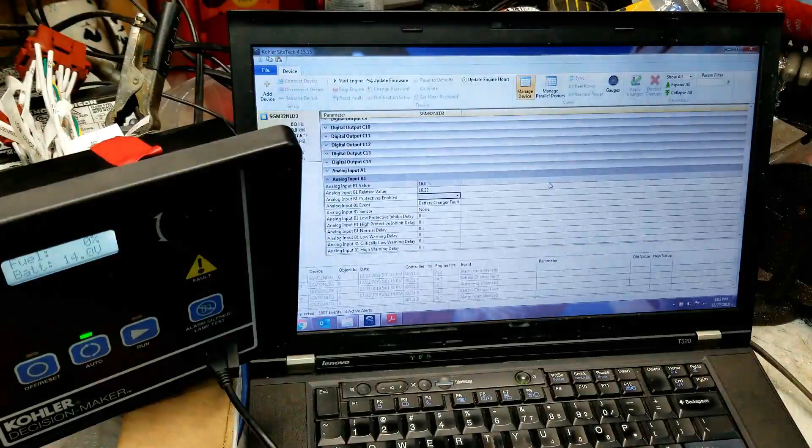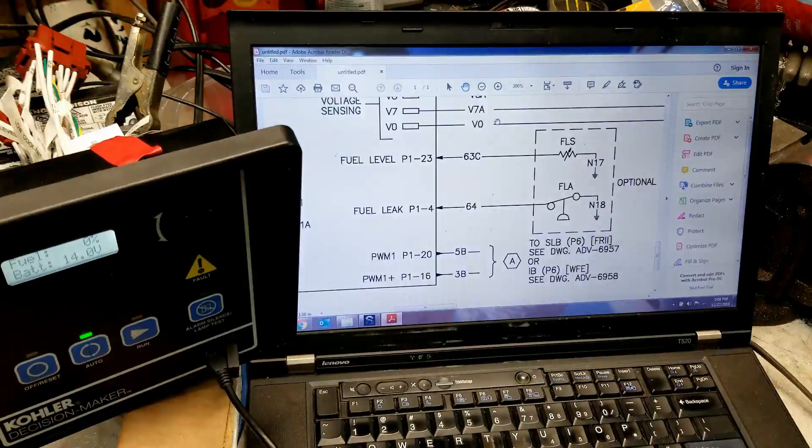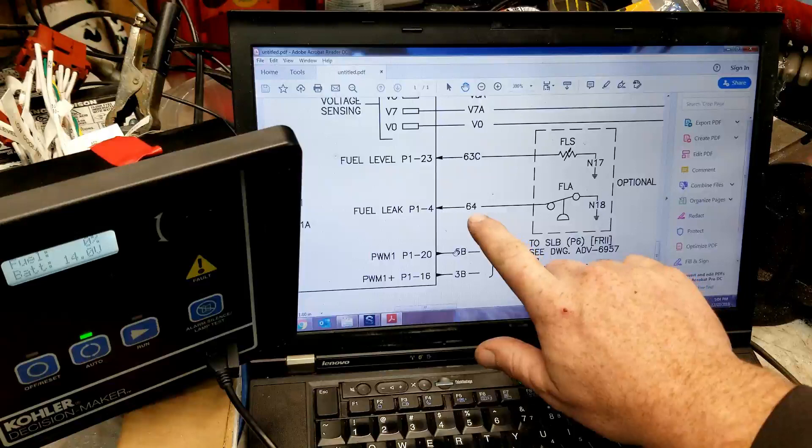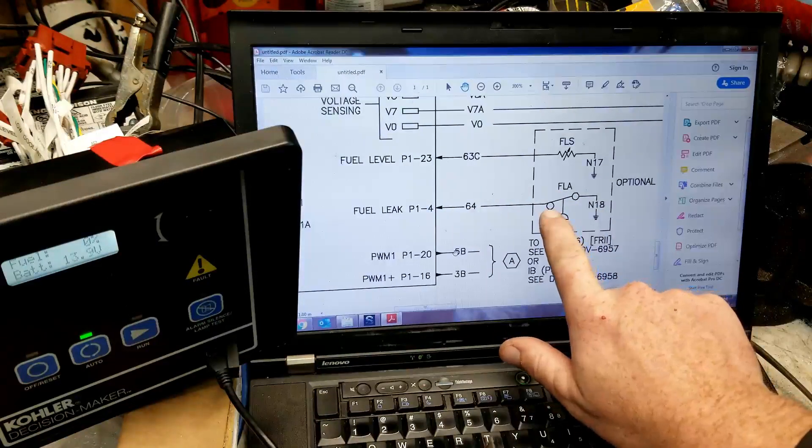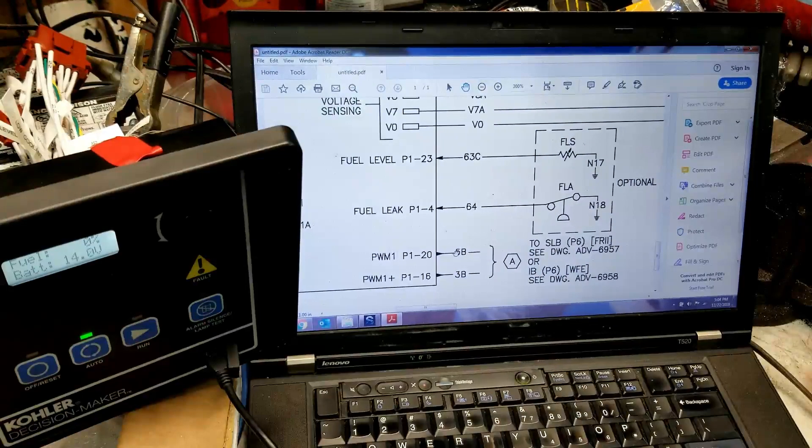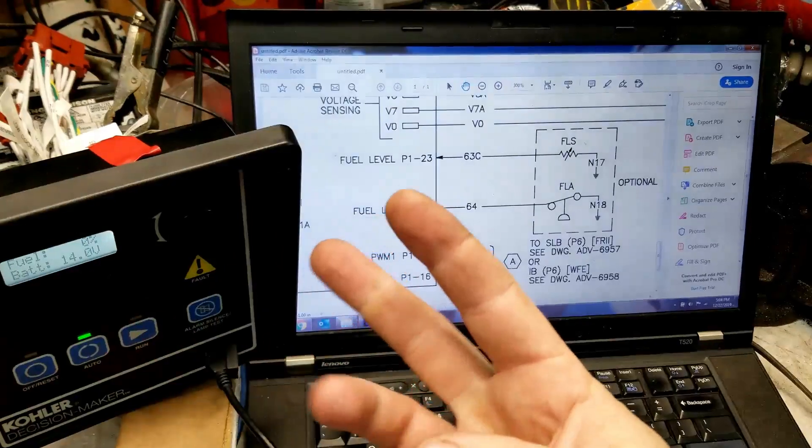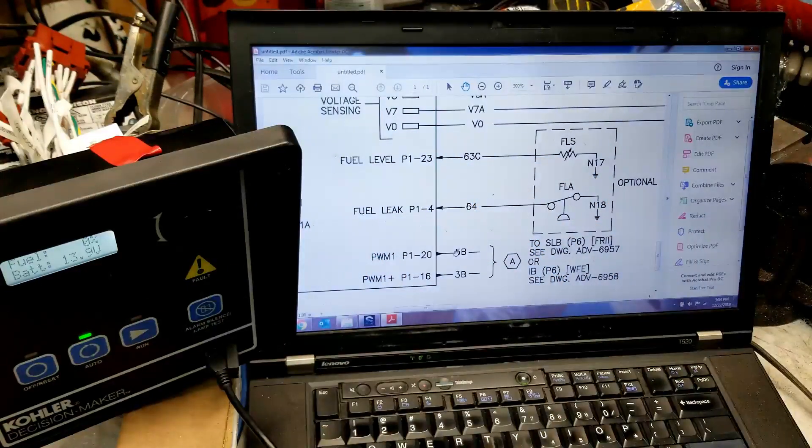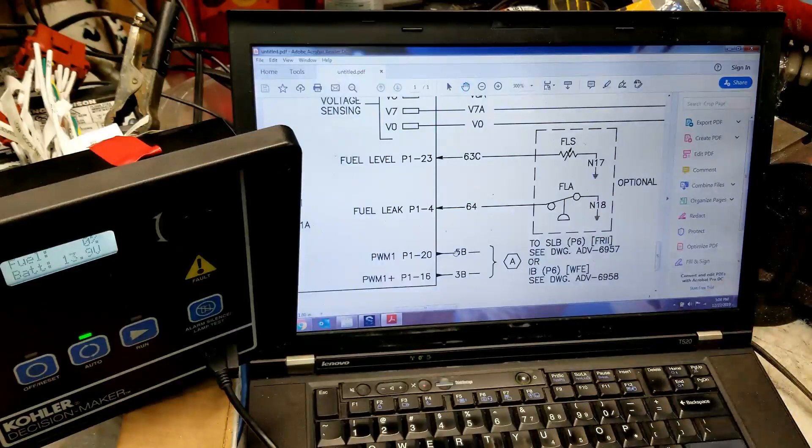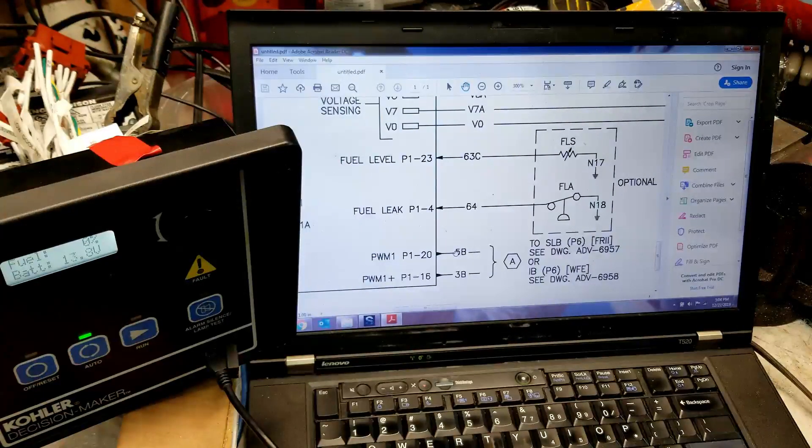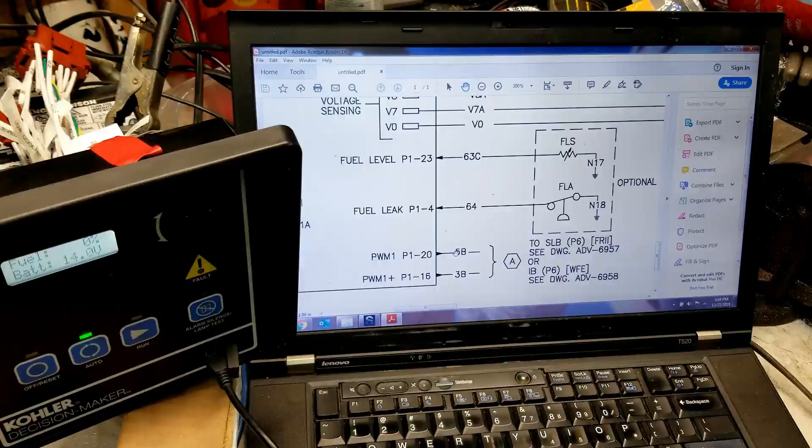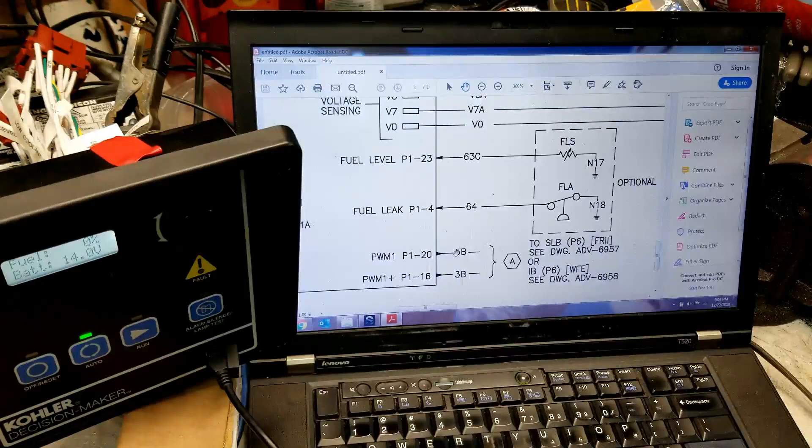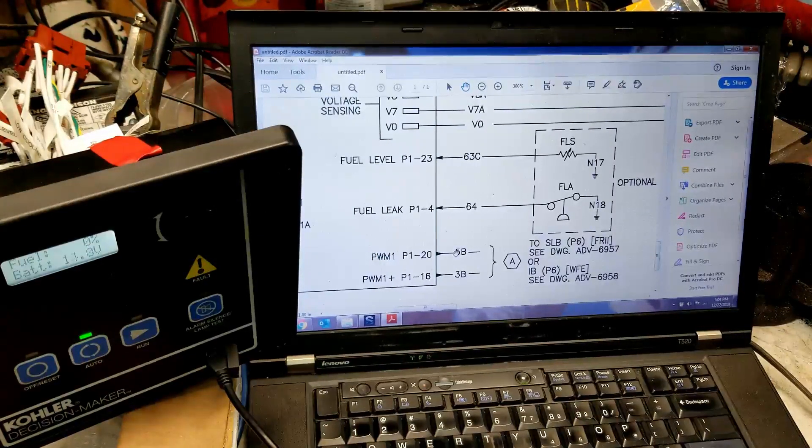So, first of all, if you go over to P1-4, which is wire 64, that could be your fuel leak alarm. That'll get rid of one for you. Then you come over this controller, you have three digital inputs. So you got, boom, you just wiped four off the table. So you come back over this board, and boom, you have two more inputs. So you're just barely scraping the table with it, but you're able to take care of business with what you got. Make sense? All right. You guys have a great day. Bye-byes.